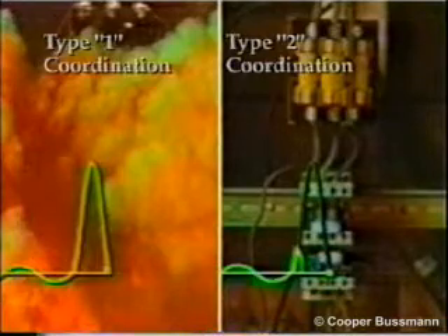Please review the following two clips and observe the difference between an arcing fault using a non-current limiting device and the same circuit using a current limiting device. In this test, the circuit is protected by a non-current limiting power circuit breaker with the short time delay set at 12 cycles. This unfortunate worker may never go home again.